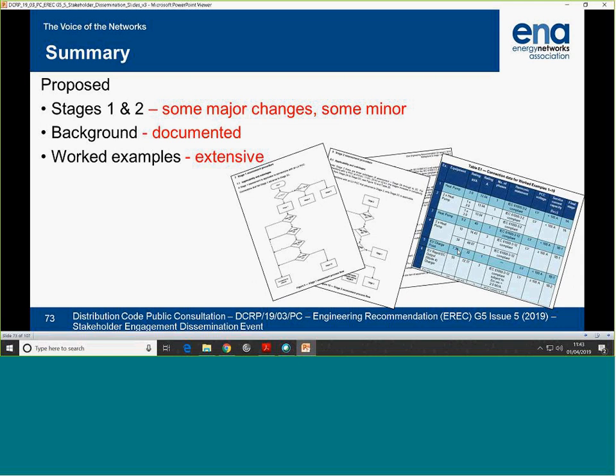Yeah, one of the major comments for me is you've obviously brought active front ends in, which are a new technology. There are other technologies that have also come in since G5.4-1, like active filters. The feedback we were given when we put this out to yourselves was that it's implicit, but nothing appeared very implicit to me. Not all manufacturers have an active front-end version, and some that do will use it very much as a marketing point: now you can use an active front-end to get you G5.5.